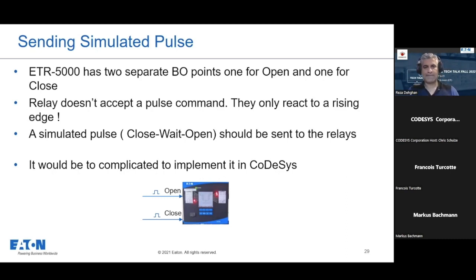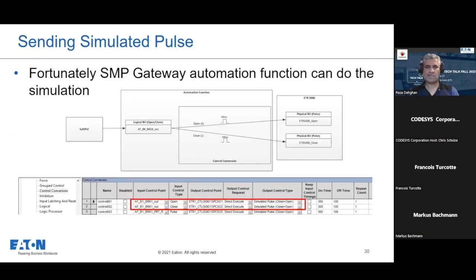Next page. So yeah, the way it works, and this is a built-in function in SMP Gateway automation function. It gets the command on one binary output that can be a 0 or 1, and then internally it will change the command. It basically creates two separate points, and on each of them it can simulate the pulse using close, wait, open. And you can see it on a screenshot on the bottom of the page.